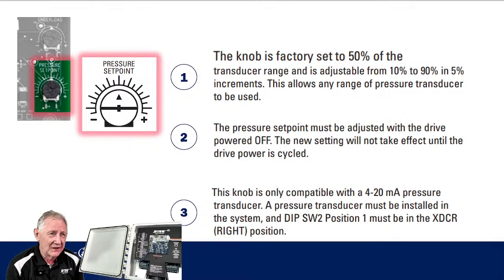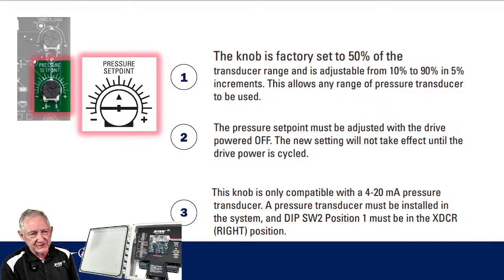So basically, if we have a 100-pound transducer, we are saying that you can adjust that range from 10 to 90 PSI. That's what we're saying, 10 to 90%. That'll come in 5% or 5 PSI increments if it's a 100 PSI transducer. But there are other transducers that can be used on these drives, and on occasion they will be. Those could be 150 or 200, sometimes 300 PSI. This still applies. When we talk about 10 to 90% of a 150-pound transducer, that's no longer 10 to 90 PSI like it would be on a 100-pound, right? So you do the math. But that's what that transducer dial is going to do: it's set for a percentage of the range of that transducer.